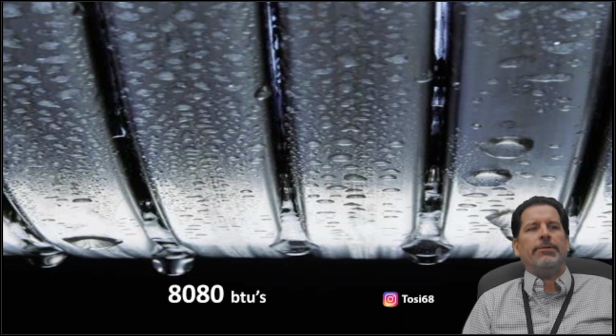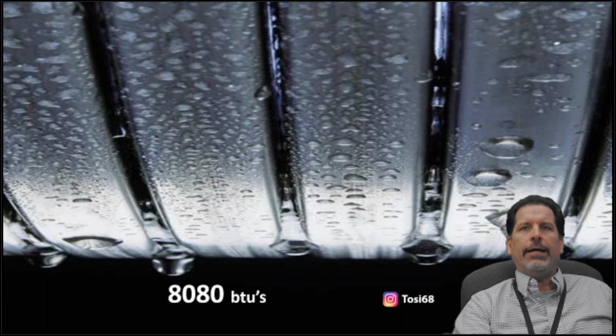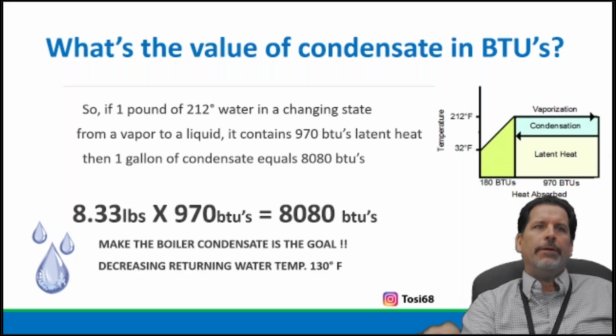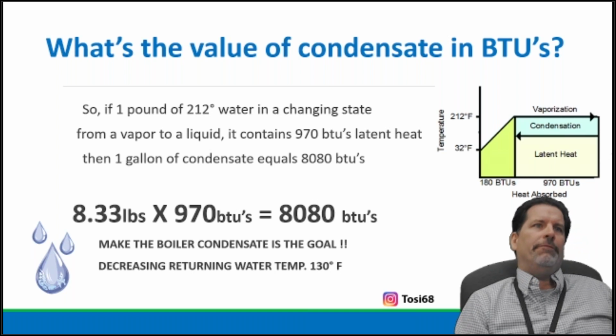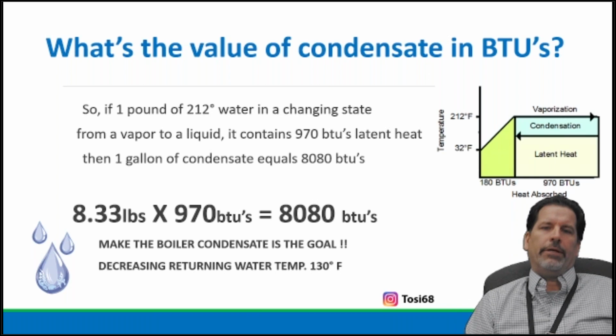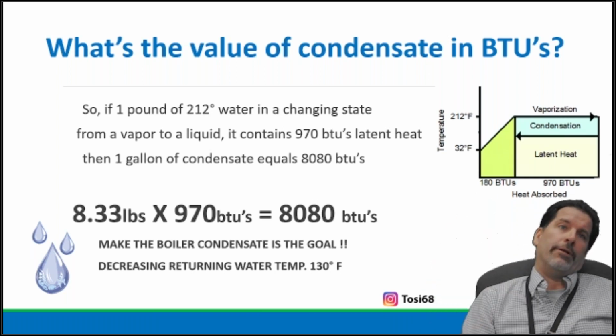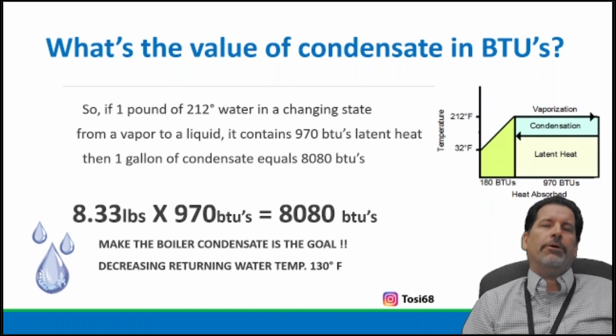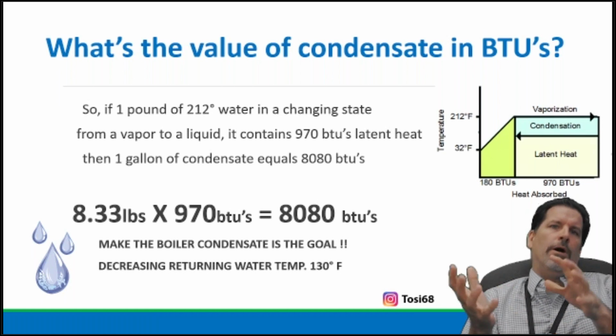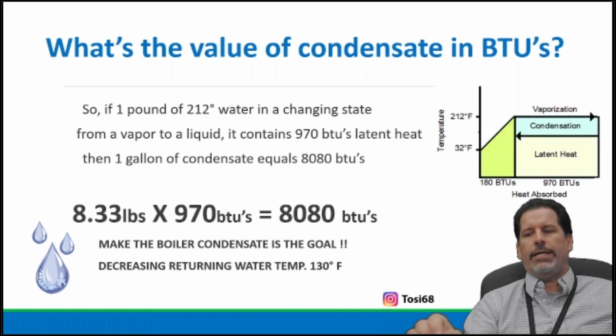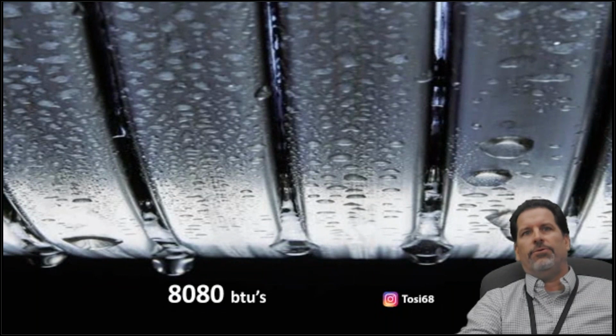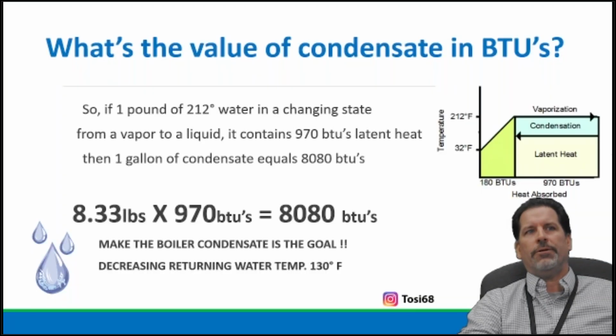8,080 BTUs. Anyone know what that represents? 8,080 BTUs. Why is that a magic number, and why do we care? Well, the value of condensate in BTUs, that's what that 8,080 BTUs is. A pound of 212 water changing state, from a vapor to a liquid, sounds like our flue products wanting to leave the space, right? It contains 970 BTUs of latent heat. Just that 212 vapor to 212 liquid gives off those BTUs. That liquid is running back down and washing across our heat exchanger, right? There it is. That's what we want to achieve, lowering water temperature.